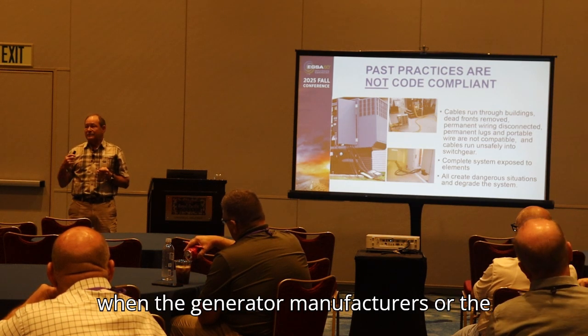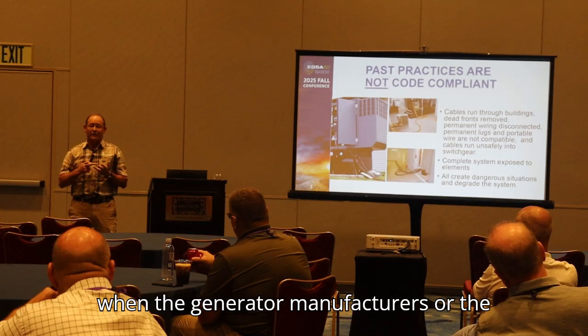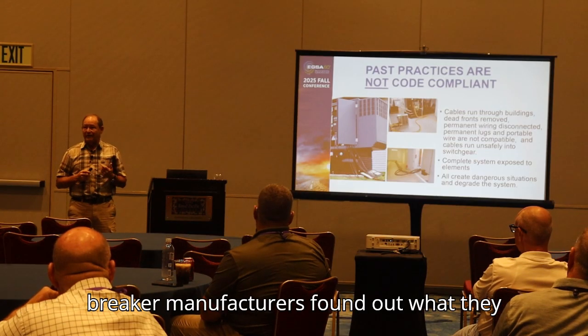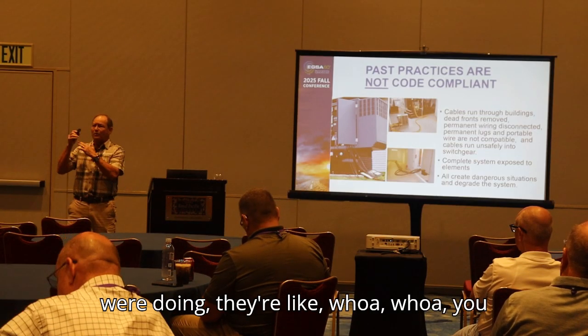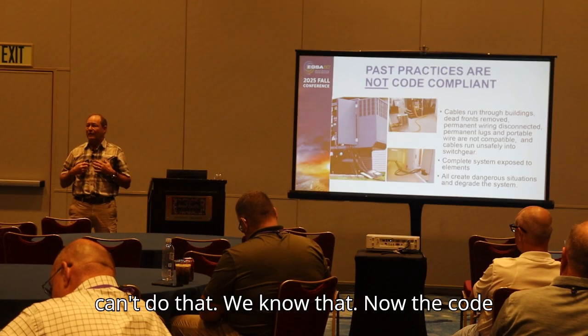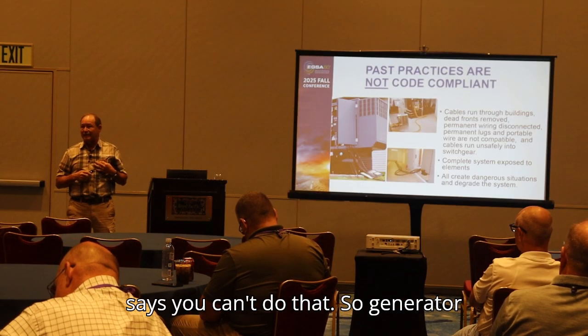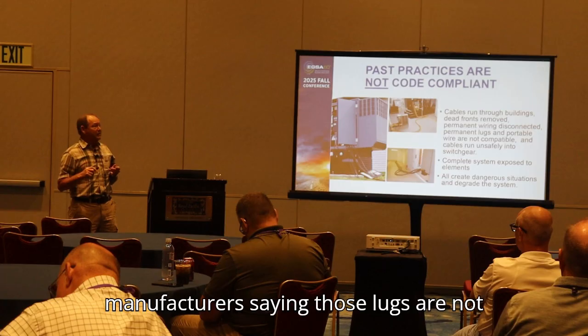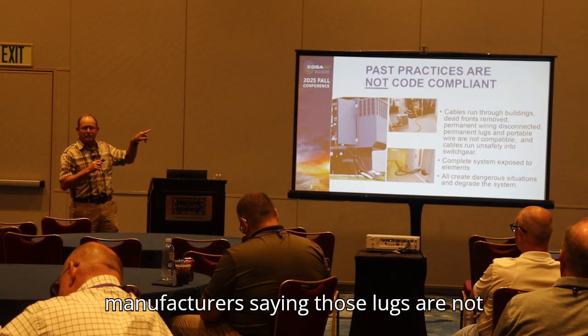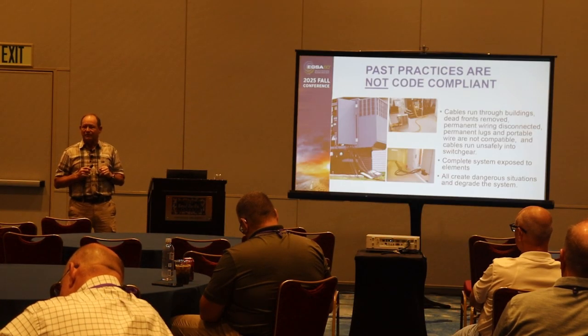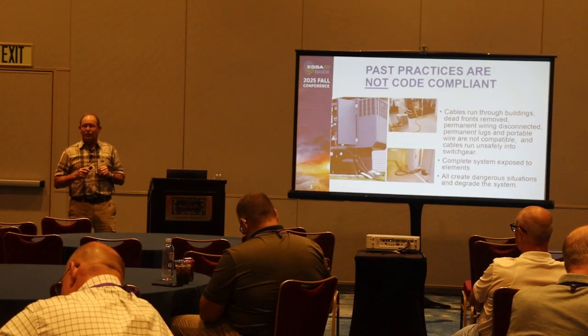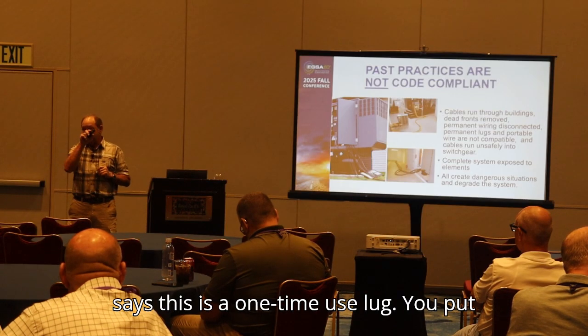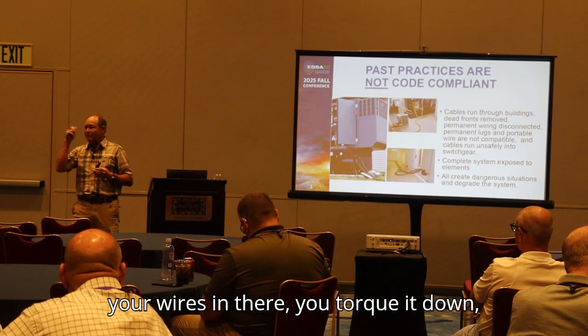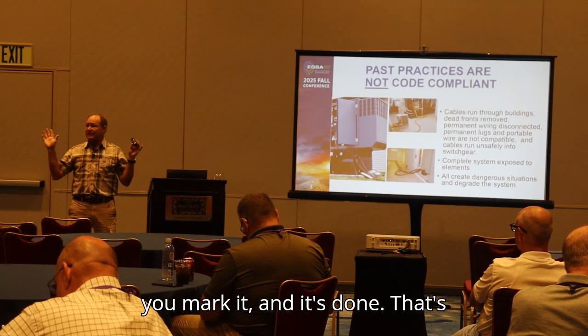When the generator manufacturers or breaker manufacturers found out what people were doing, they said, whoa, you can't do that, we know that, now the code says you can't do that. The generator manufacturers say those lugs are not for repetitive use. You have to put a label on there that says this is a one-time use lug. You put your wires in, torque it down, mark it, and it's done.